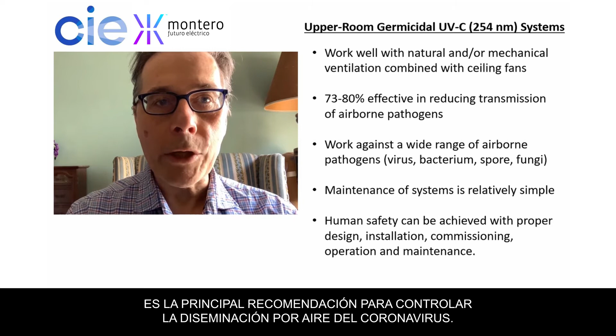A secondary airborne strategy would be through the ventilation circuit. Many hospitals with mechanical ventilation recirculate their air about 15 times per hour, so having a germicidal UV lamp within the air duct itself is a good strategy for secondary disinfection of virus that may have escaped the upper room application.